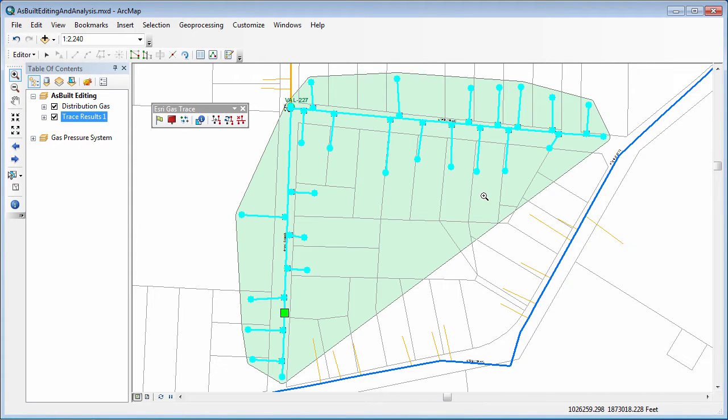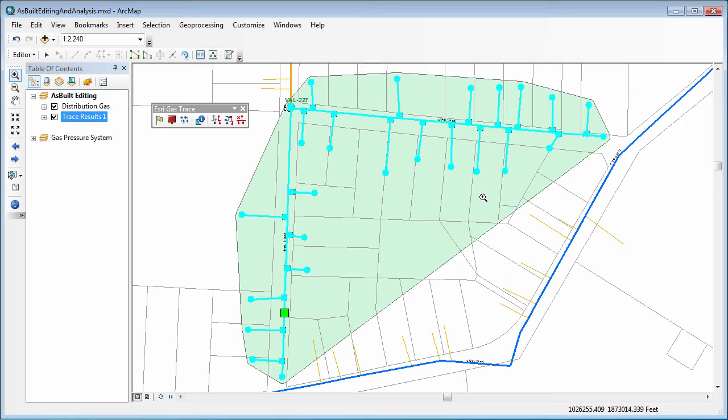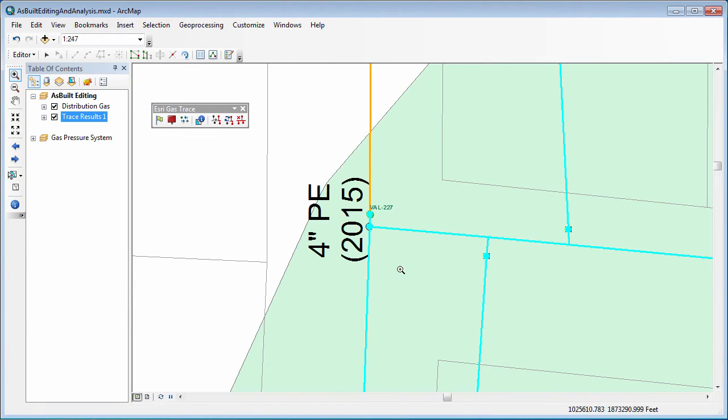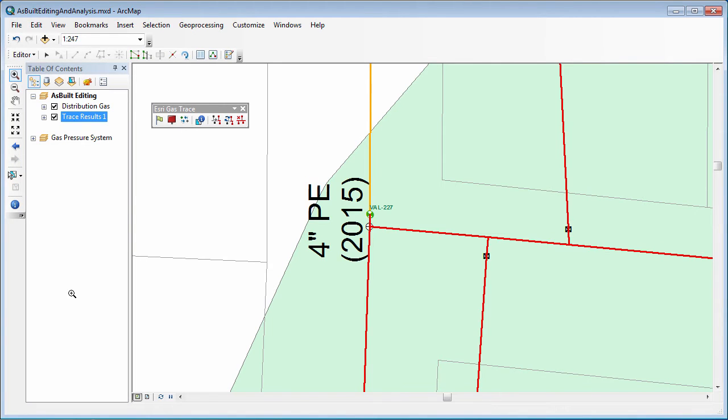The next key piece of a valve isolation trace would be able to mark a given valve as not being operable, so mark it as inoperable. It could be paved over or any other issue, maybe it's not even a critical valve. We can filter, by the way, on only critical valves within the configuration for the tool, but for right now we just want to mark this specific valve here, and I'll zoom back into it, as inoperable. So I'll go ahead and clear my selection.